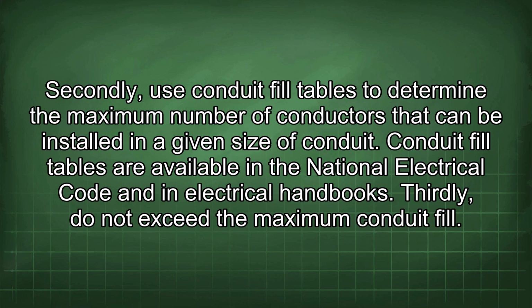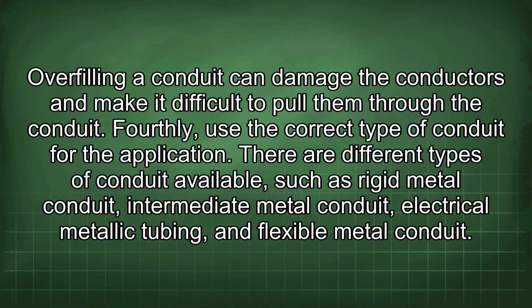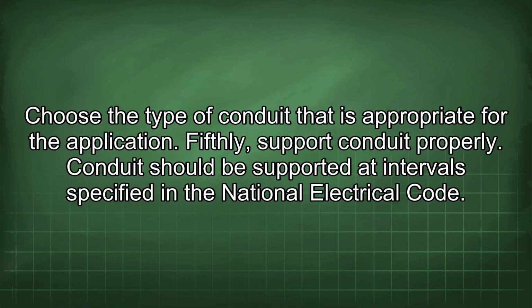Secondly, use conduit fill tables to determine the maximum number of conductors that can be installed in a given size of conduit. Conduit fill tables are available in the National Electrical Code and in electrical handbooks. Thirdly, do not exceed the maximum conduit fill. Overfilling a conduit can damage the conductors and make it difficult to pull them through the conduit. Fourthly, use the correct type of conduit for the application. There are different types of conduit available, such as rigid metal conduit, intermediate metal conduit, electrical metallic tubing, and flexible metal conduit. Choose the type of conduit that is appropriate for the application.